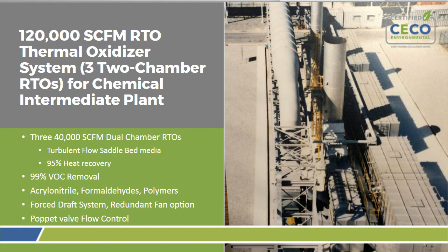Typically, what they're doing there is acrylonitrile and polymers. It is a forced draft system. There are redundant fans on each of the 3 RTOs. 2 of the RTOs share a common stack. The customer wanted this designed in, but you can see there's the collection system with the duct. 95% heat recovery, and these had turbulent flow saddle media.